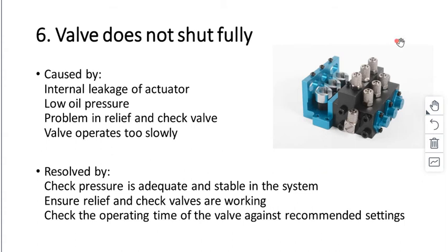The valve does not shut fully. Could be another problem. So again, this could be caused by an internal leakage of the actuator. It could be low oil pressure. Or it could be a problem in the relief and check valve. So for example, if the relief valve is set too low, the oil pressure is going to go too low as well, and it may not be enough pressure to operate the valve successfully. Or the valve operates too slowly and you don't get the action which you require.